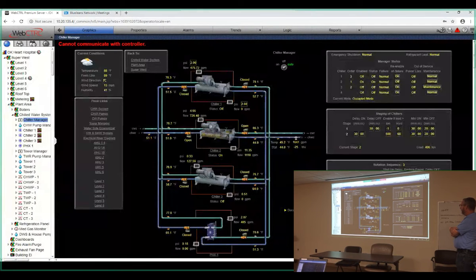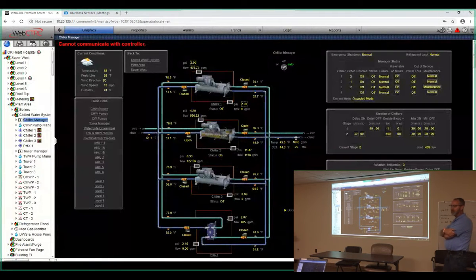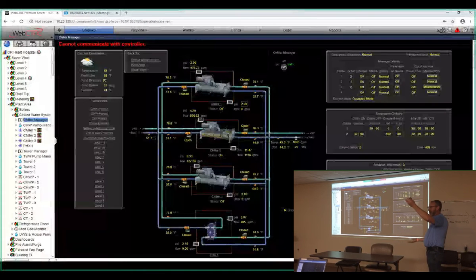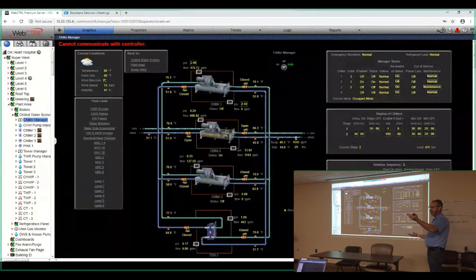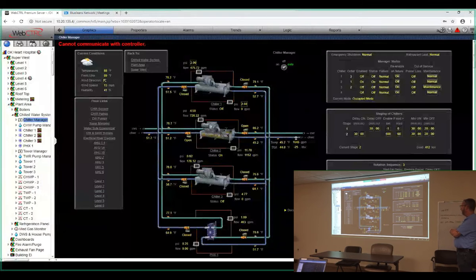And behind that, we've got some startup delays and delay off. So when we rotate, how do we bring the chiller up? Startup is going to be a 30-second delay. When I go to shut down, if I go from one stage to another, we've got a 1-minute delay to stage down.